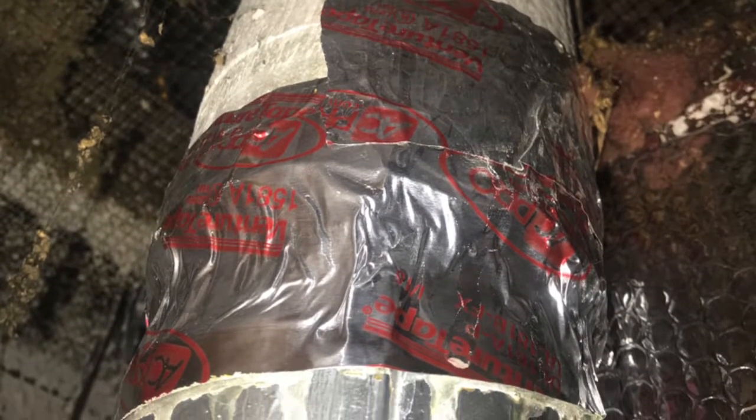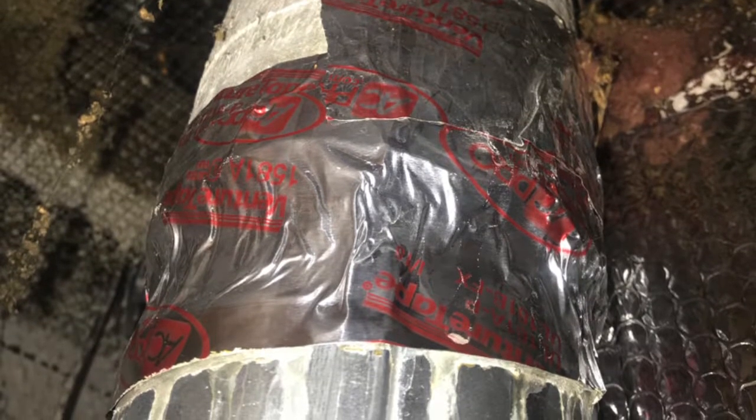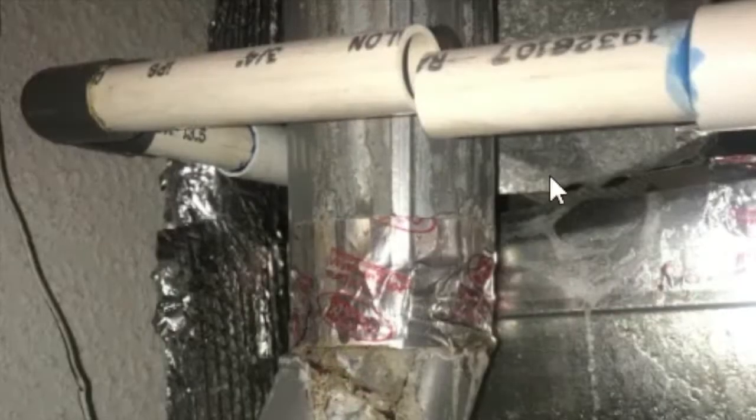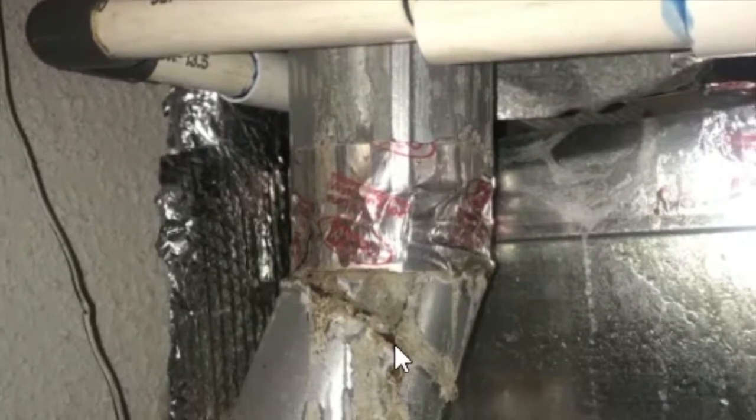You will get condensation forming in the vent, and the corrosion or moisture that is coming down the vent pipe is highly acidic and can corrode out the vent pipe as well as the inducer motor and firebox inside the furnace. You can see here that there has already been dripping from the transite vent.